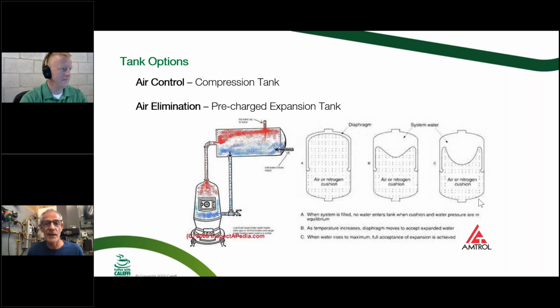And what we mean by that is that little air bubble that we're kind of indicating there as a red in that picture needs to stay in there. We got to control or manage that air bubble because that's our expansion. If that goes away and the tank becomes waterlogged, then we lose the ability to have expansion space, and we're going to pop a relief valve. So you got to pipe those properly. There's a couple little valves that they've added into these that you can make them work a little bit better so they don't thermal siphon all your heat out of your boiler.